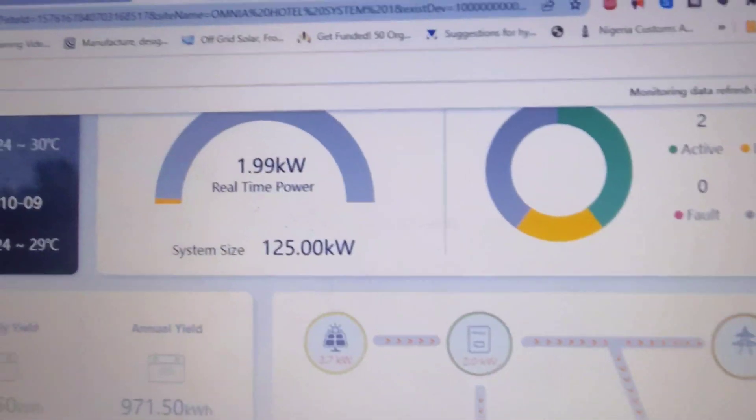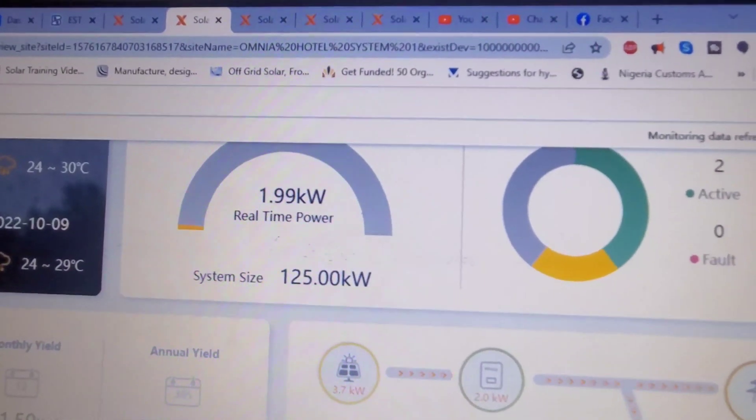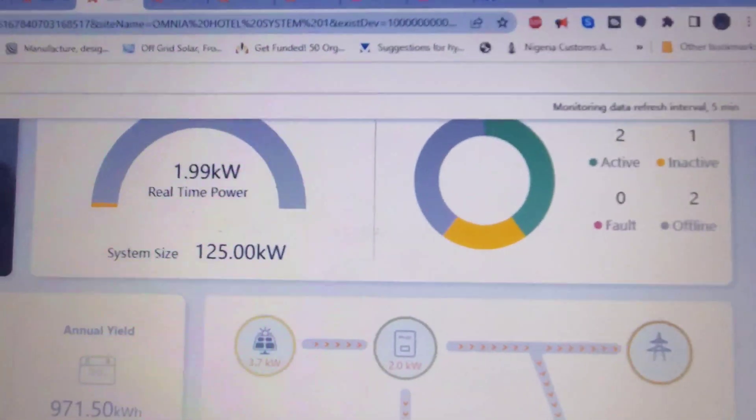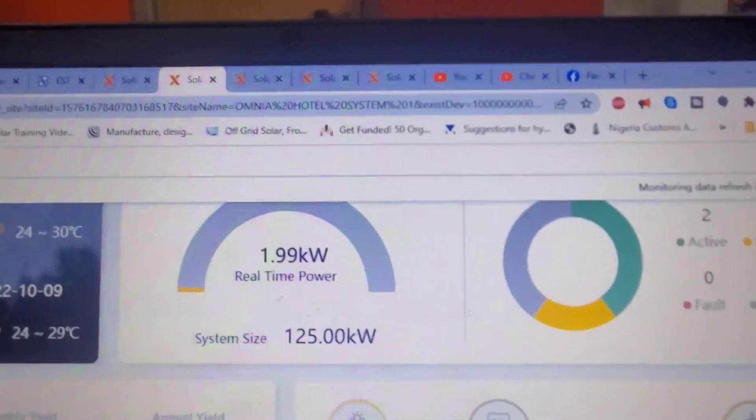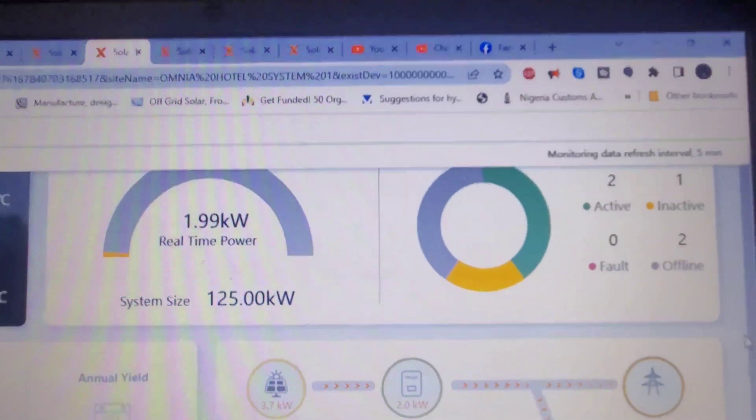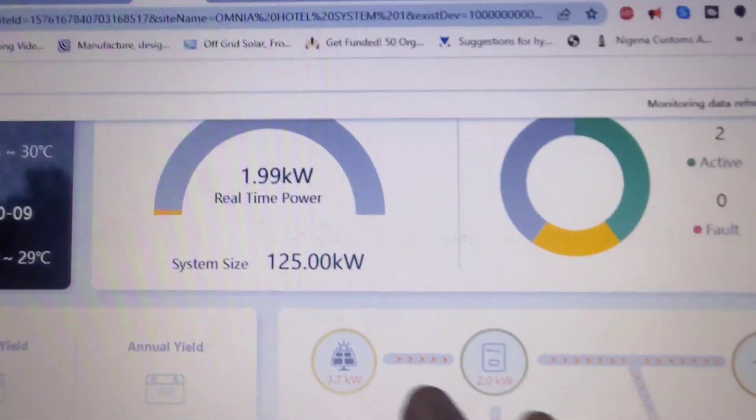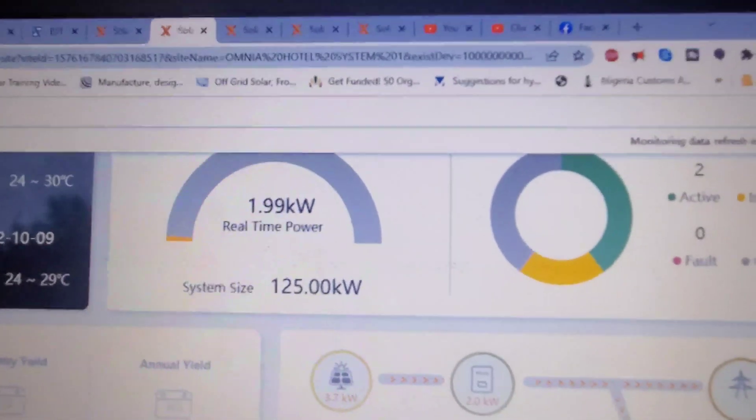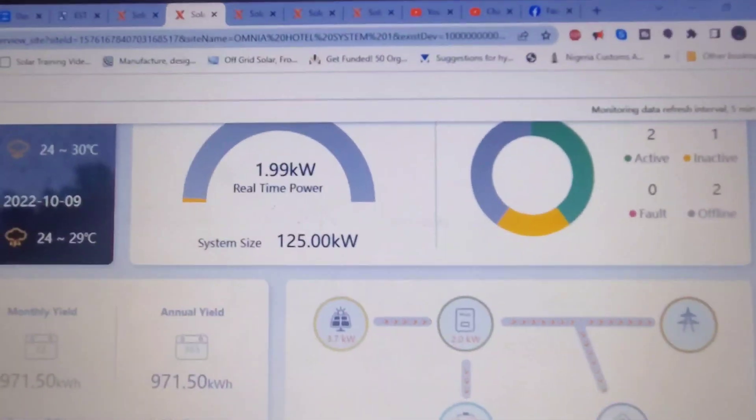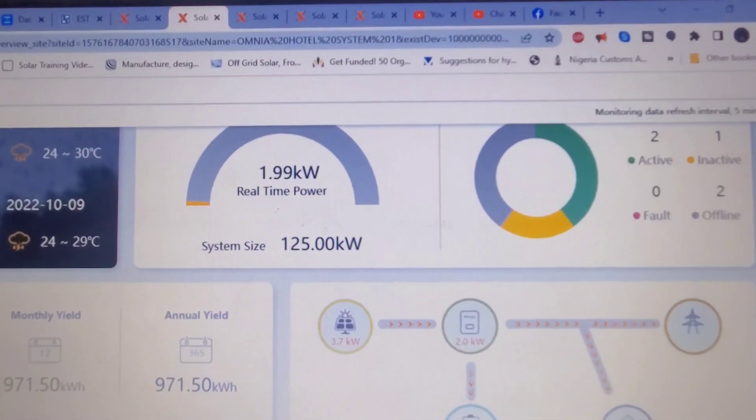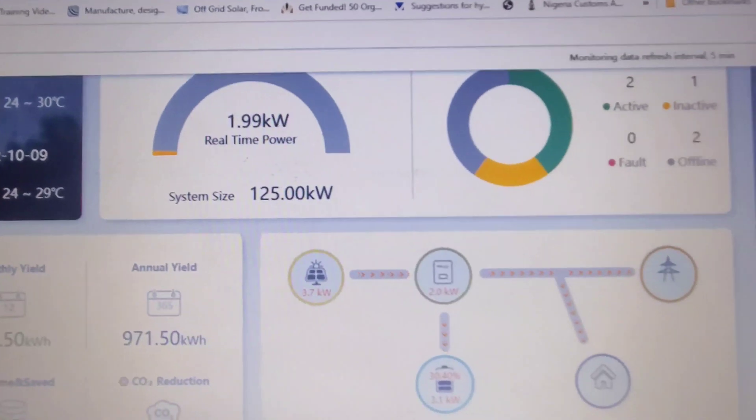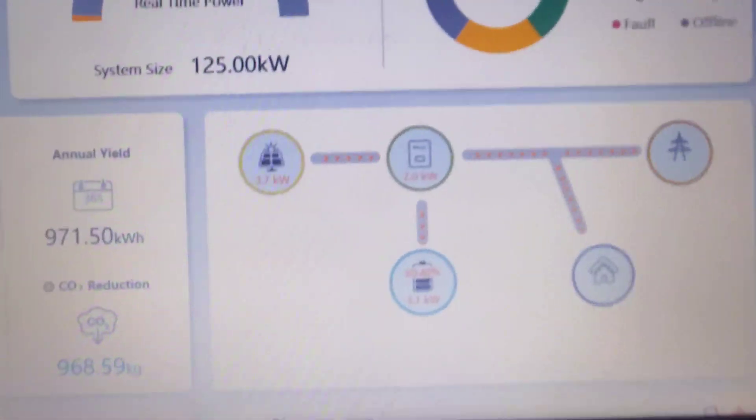Let's start with Omnia One. There are two systems, both with six inverters of 15 kilowatts. Right now we only have five inverters of 15 kilowatts. We've been seeing 50 kilowatts on this system. We added additional batteries yesterday and they're not balancing, so we're struggling. It takes two or three days to get the batteries to balance.